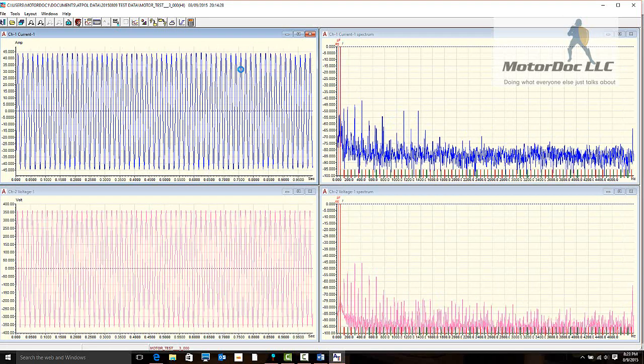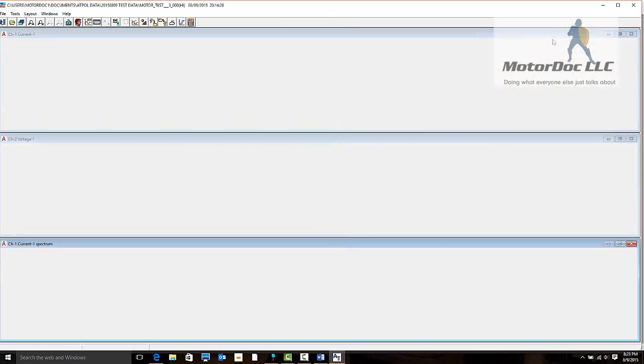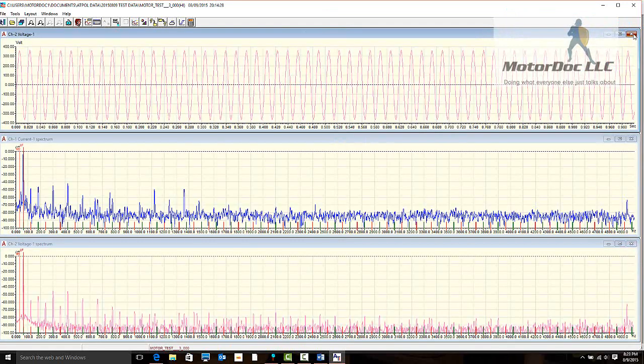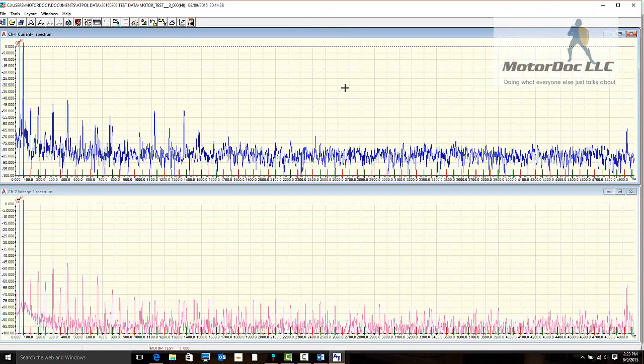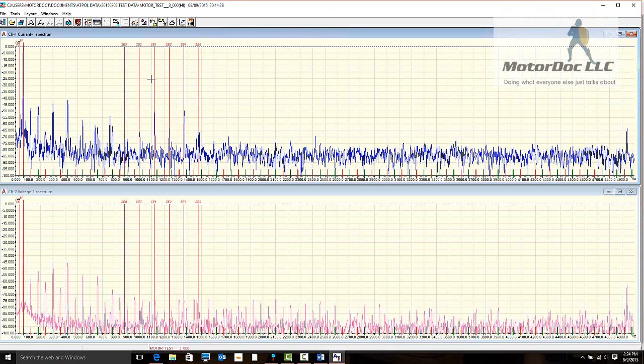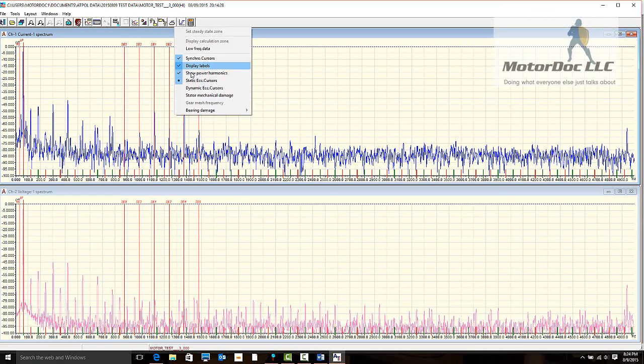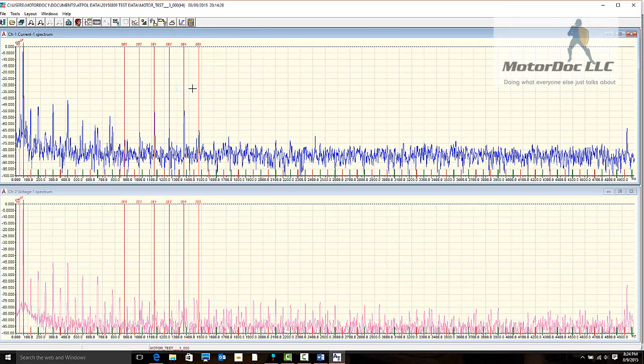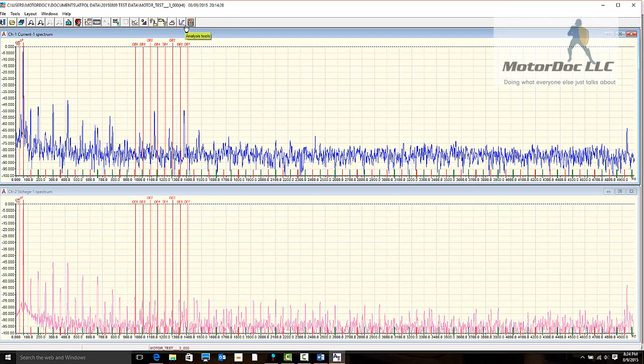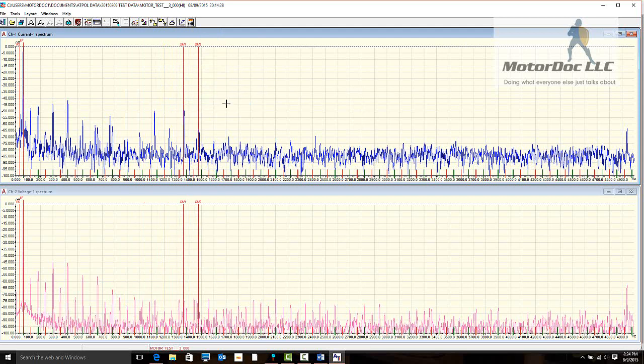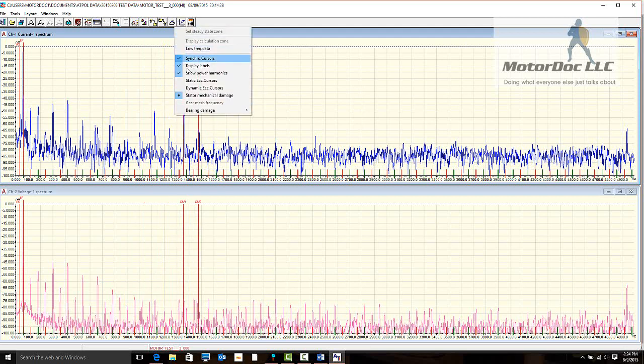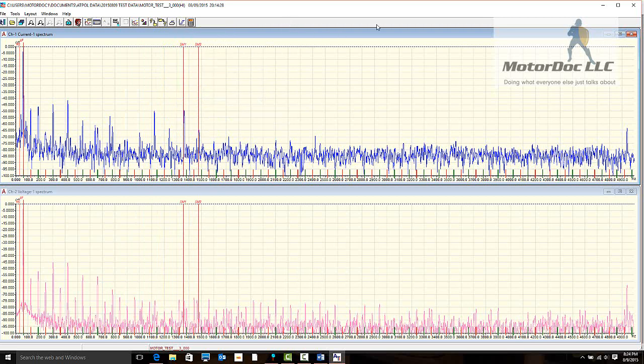Again we're zooming in. Let's get rid of this noise. And let's take a look. Static eccentricity cursors, very definite. Dynamic eccentricity, not there. Stator mechanical, it looks like there might be something. And we had already seen the varying conditions. So with this, I hope you've enjoyed your tour.